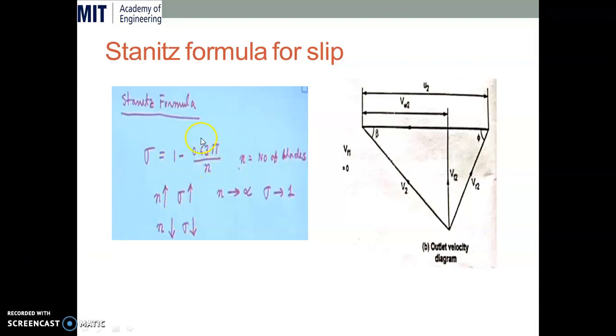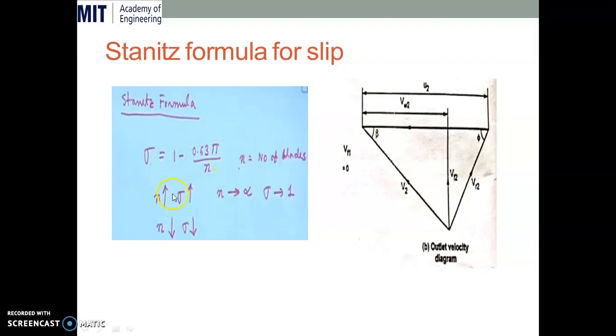There is an empirical formula for slip called the Stanitz formula: sigma equals 1 minus (0.63π / n), where n is the number of blades. As the number of blades increases, the ratio 0.63π/n decreases, so sigma approaches 1 — meaning the slip factor increases toward 1. Conversely, if the number of blades decreases, the ratio increases and the slip factor becomes less than 1 and decreases. Ideally, we want to minimize the slip factor to reduce work input and losses. This is the Stanitz formula for understanding slip in a centrifugal compressor.